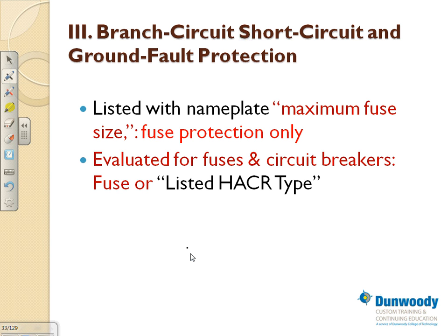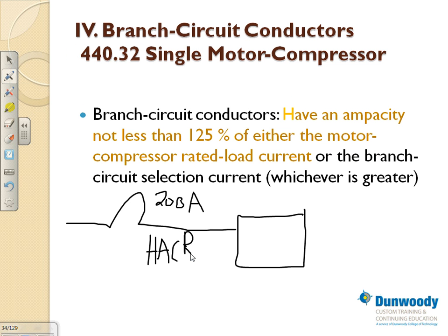Instead of having an unfused disconnect, now you have a fused disconnect. And you continue to have your own circuit breaker in your panel. You're not going to go change the panel just to match an HVAC equipment that says it needs a fuse. You keep the circuit breaker to protect your cable, with the fuse disconnect right next to the equipment based on the specification of the manufacturer, and off it goes.